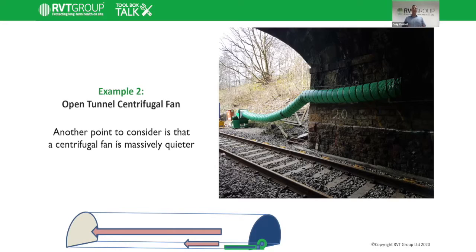Simply sitting a fan outside of the tunnel and just blowing air at the face of the tunnel is not a good way to ventilate. Effectively, what you're doing is just creating a massive turbulence around the tunnel mouth, and it's a very, very noisy and inefficient way of ventilating a tunnel. You need to be maintaining the Venturi effect, the entrainment of air. Make sure you've got that jet of air traveling all the way through the tunnel, making sure there's no way that any contaminants can build up.